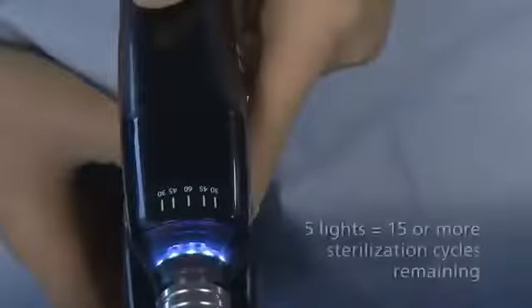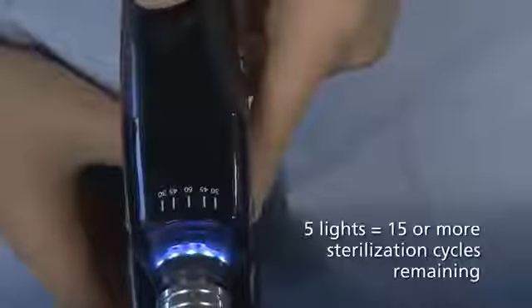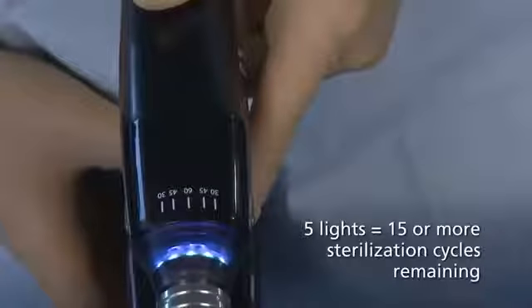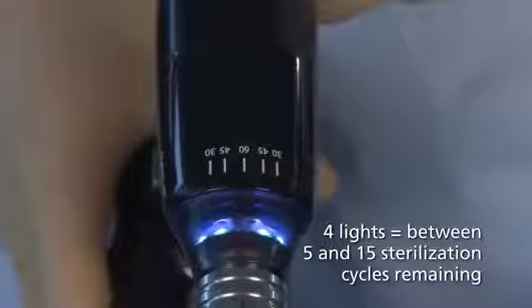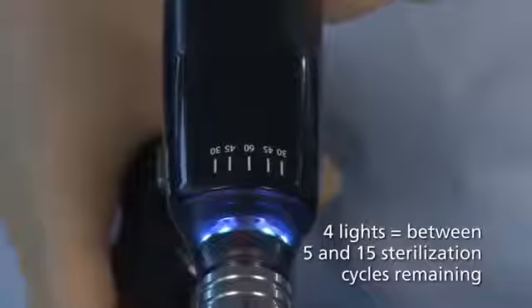Once calibration is complete, the white firing progress indicator lights on top of the handle show the relative number of sterilization cycles remaining on the adapter. If 5 white lights appear, then the adapter has 15 or more sterilization cycles remaining before end of life will be reached. If 4 white lights appear, then there are between 5 and 15 procedures left on the adapter before end of life will be reached.